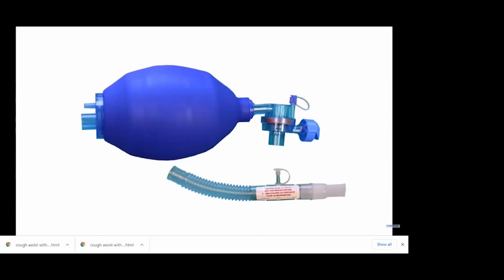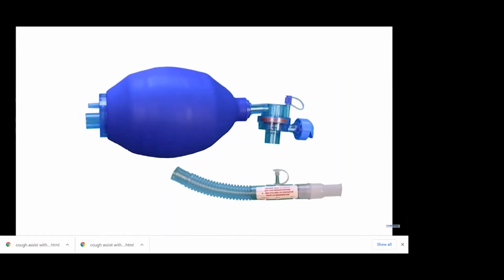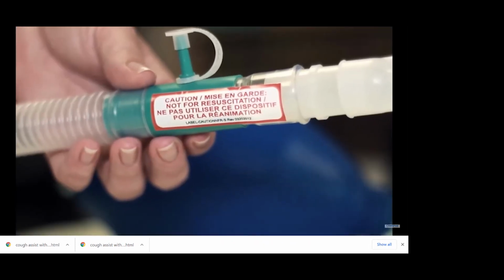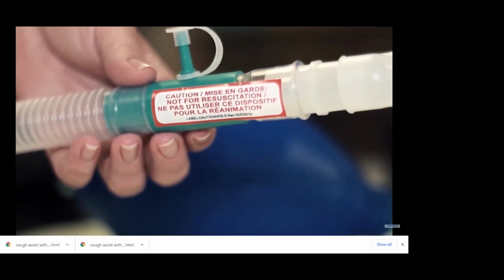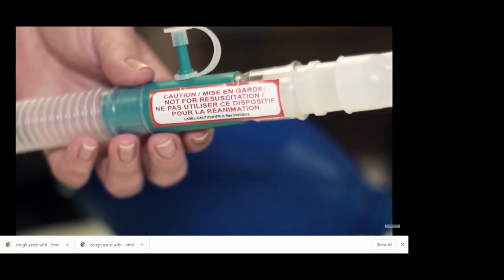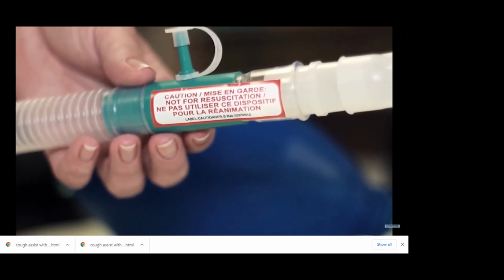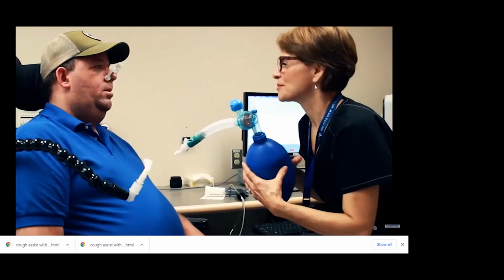Be mindful that the LVR bag is not an emergency resuscitation device. If used for resuscitation with a full face mask, the LVR bag one-way valve will not allow the individual to exhale and may cause a tension pneumothorax.